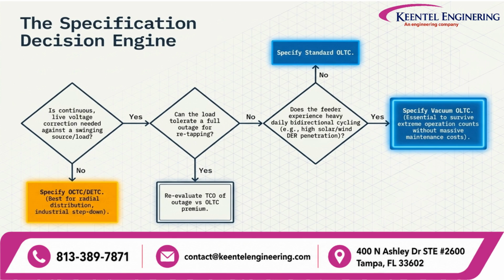First, determine whether voltage regulation must occur while the transformer remains energized. If continuous voltage control is required, an OLTC is generally the correct solution. Next, evaluate how frequently voltage adjustments will occur. Frequent changes strongly favor OLTC technology. If adjustments are only seasonal or during scheduled maintenance, a DETC may be sufficient.